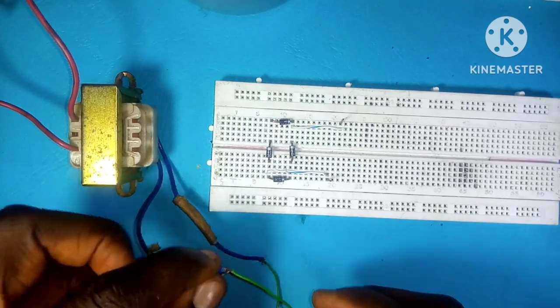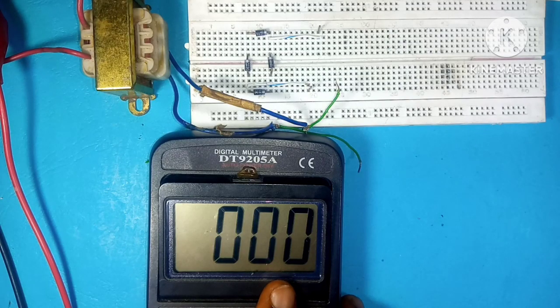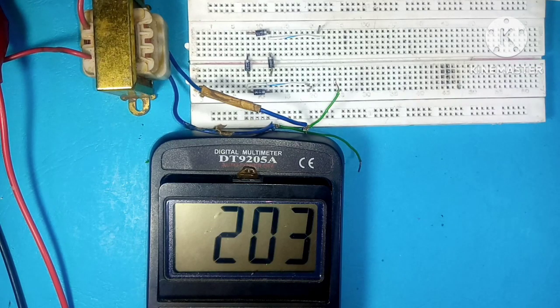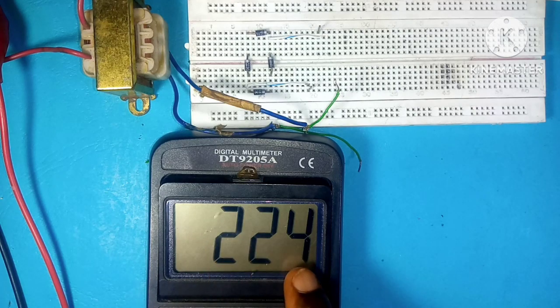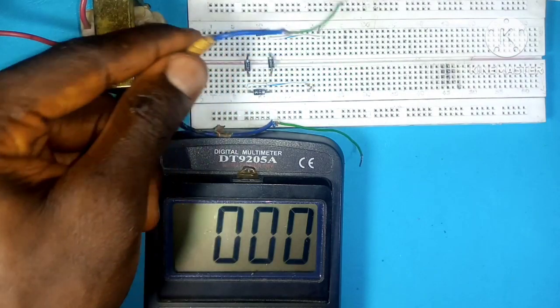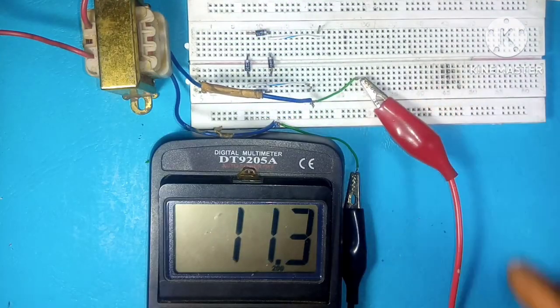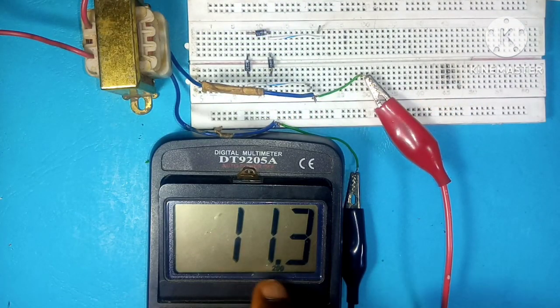It is a 12 volt transformer, but we need to know the voltage we want to operate with. You can see on the meter we have a voltage of around 224 volts, which is our supply to the transformer. But we still need to break down this voltage using the transformer so that we can have a lower AC input, and we can see a voltage of around 11.3 volts.